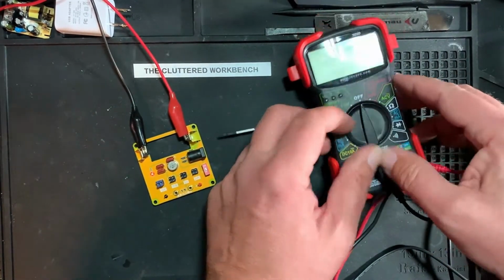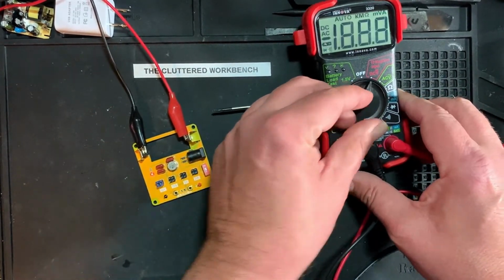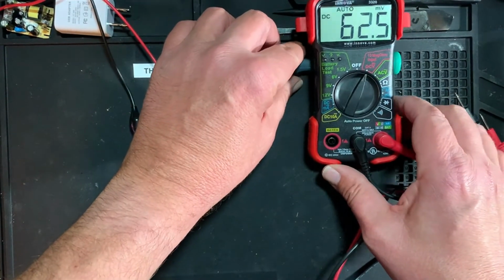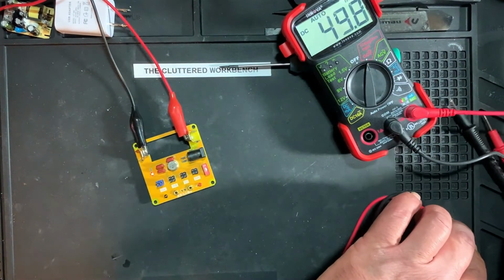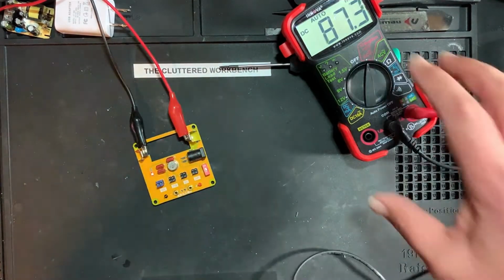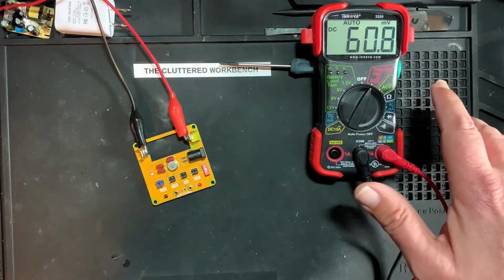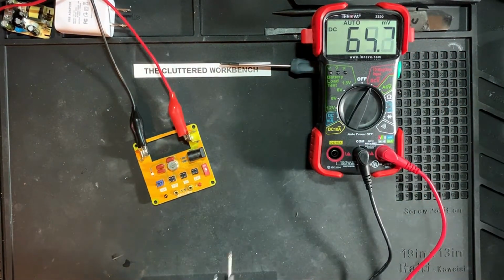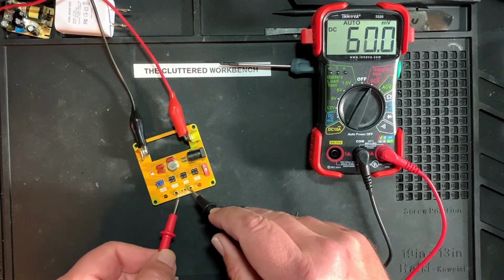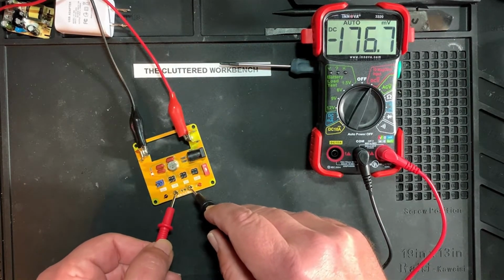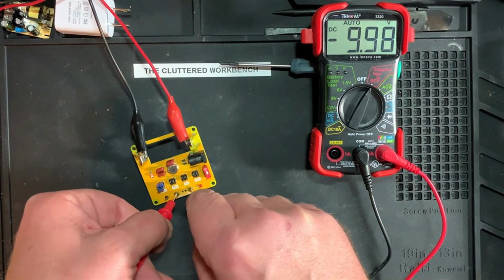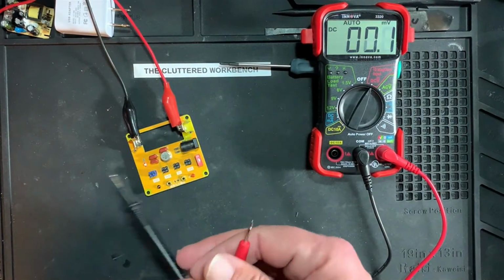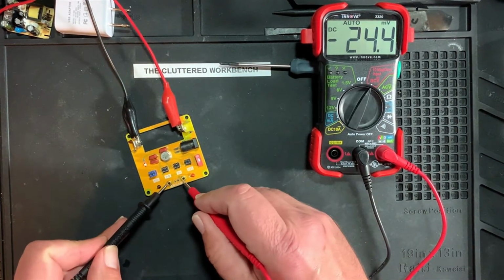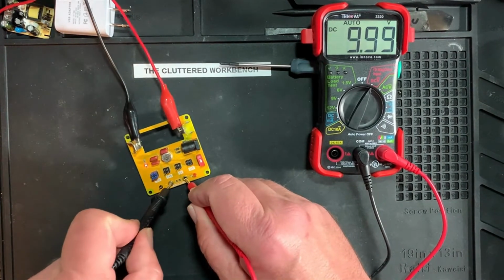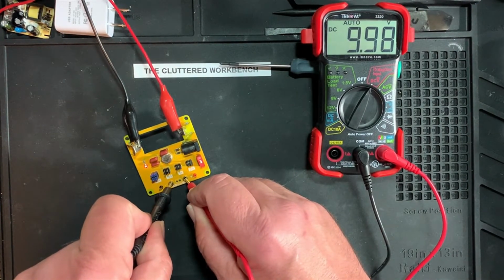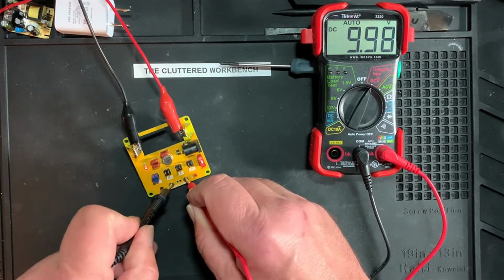Voltage standard, we'll go to DC volts. It's picking up some ghost voltage. Let me get that label. There we go. It should be set at 10 volts. Oops, across the leads. It's showing 9.98, that's not bad.